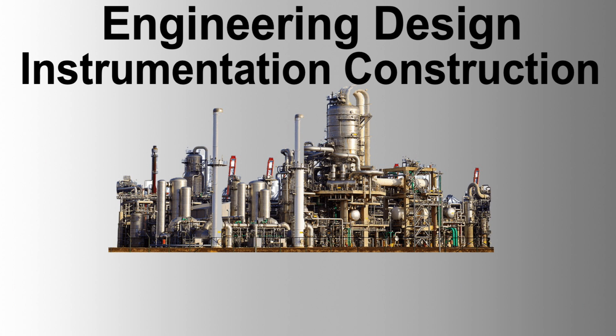Rectangular, all others. Instrument piping shall be supported from pipe supports and any other permanent structure. Instrument piping supports shall not be welded to stress-relieved equipment or internally lined equipment. Instrument piping supports shall be sufficient to maintain the instrument piping in a neat manner. Piping and tubing support. Piping or tubing and their supports shall be kept free from vibrating structures or equipment. Process piping or handrails must not be used to support instrument lines unless the drawings indicate that this is the preferred method or where prior approval is obtained from the company.